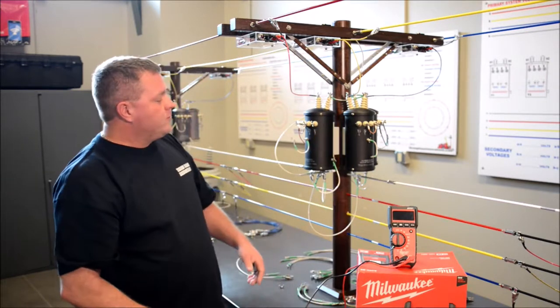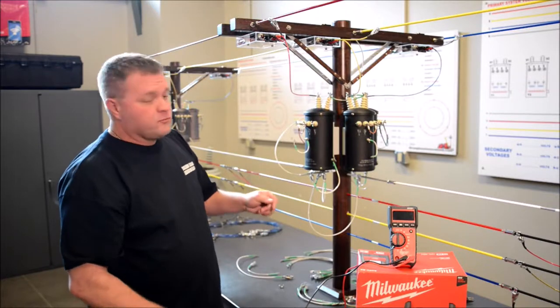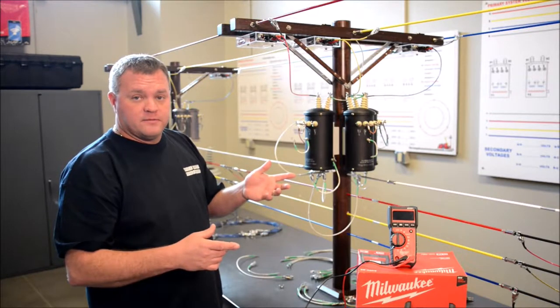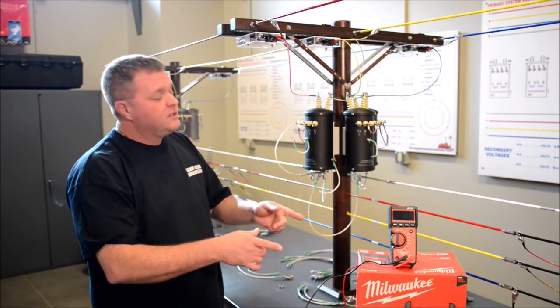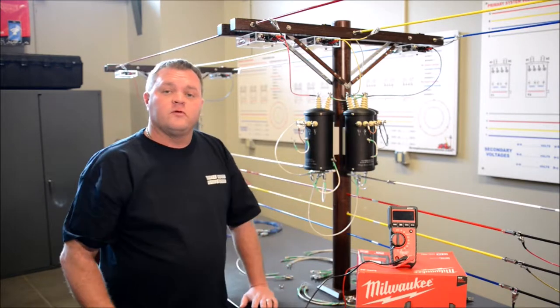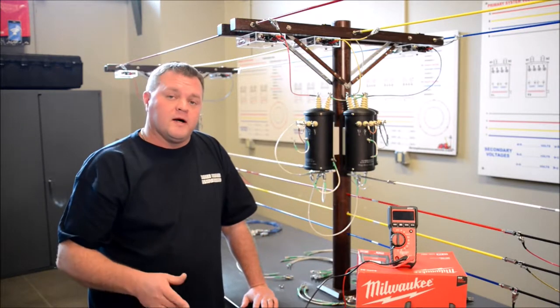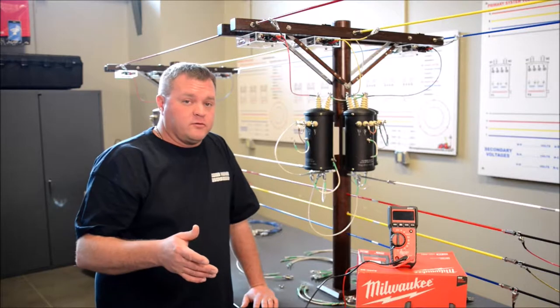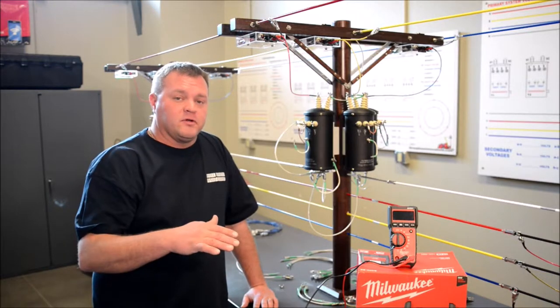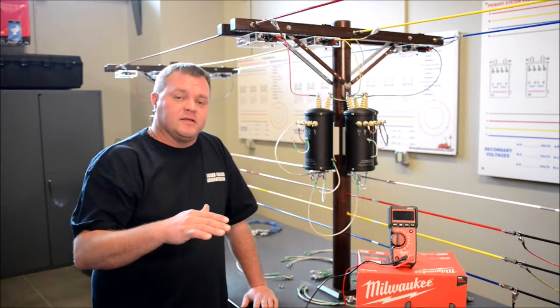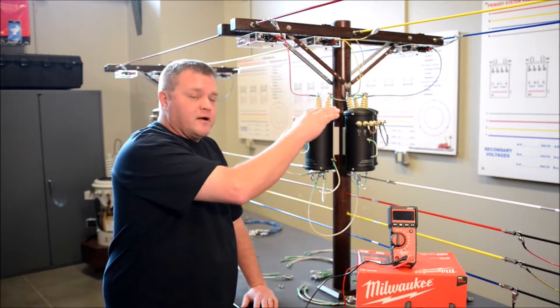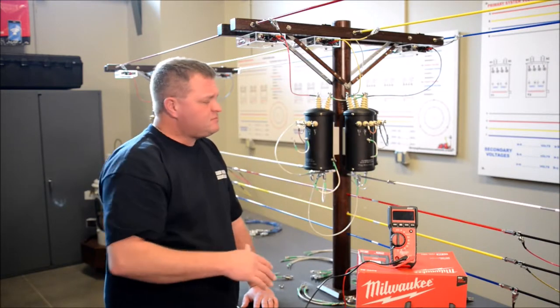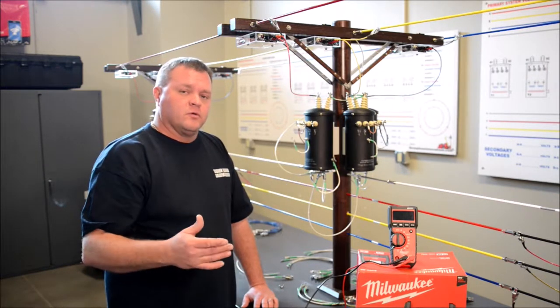So what we're going to do for this Y Delta bank is we're going to energize this here in just a second and check it with our voltmeter. Now at this test point it should be 40 volts or less for a Y Delta bank. Why is it 40 volts? There's a harmonic buildup between the Y and the Delta, meaning the Y primary and Delta secondary. If it's 40 volts or less we're good.